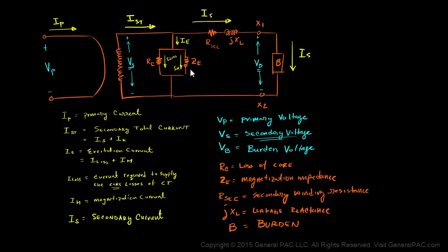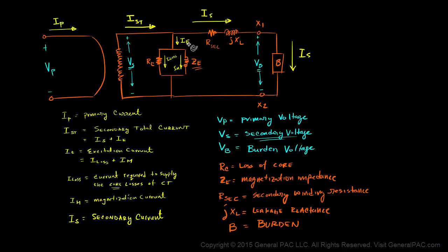The ZE value is really non-linear, which means it's going to change based off of the secondary flux. The secondary flux controls the secondary voltage, so ZE is directly proportional to the secondary voltage. During normal operating conditions, we should expect this magnetization branch to be really high — 1,000 ohms to 10,000 ohms. So during steady state conditions, the magnetization impedance should be very high, the exciting current should be very low, and the total secondary current should closely equal the secondary current. For a current transformer, the secondary current is directly proportional to the primary current based off of the CT ratio.